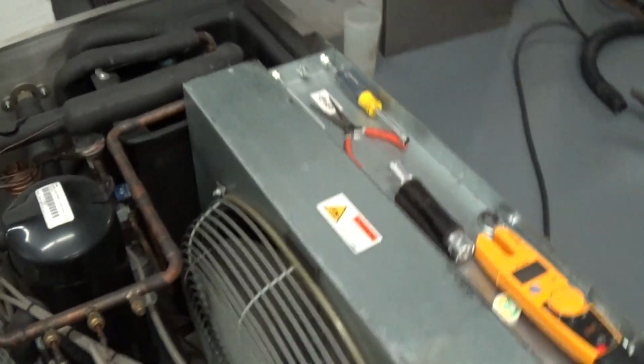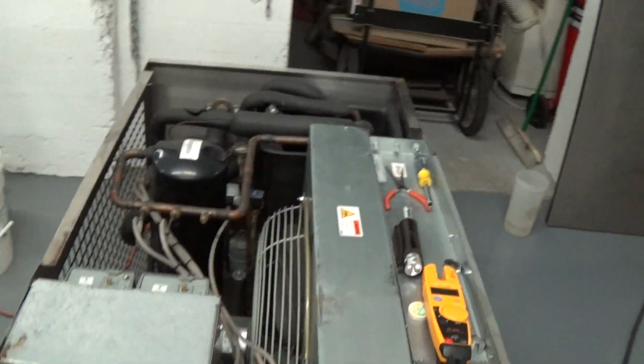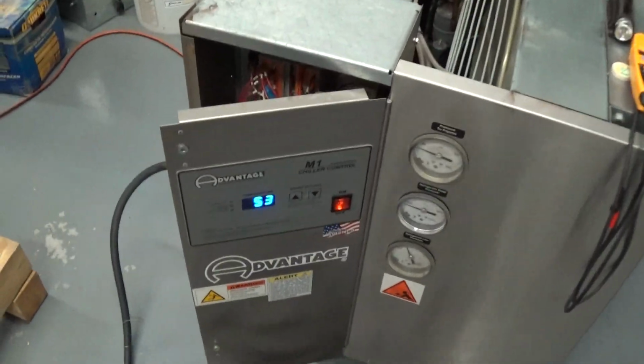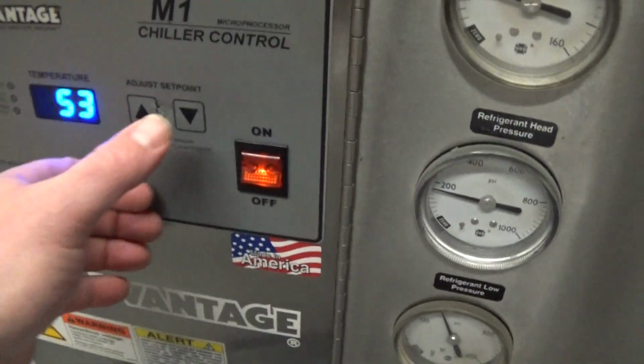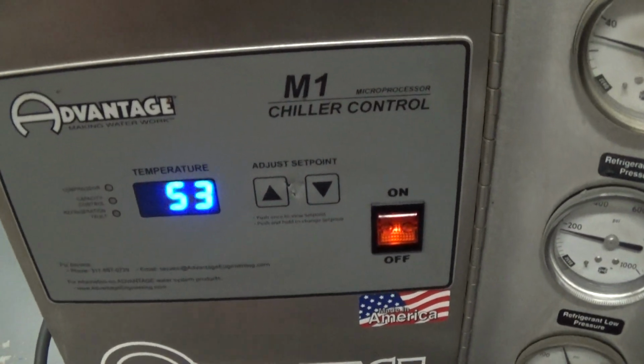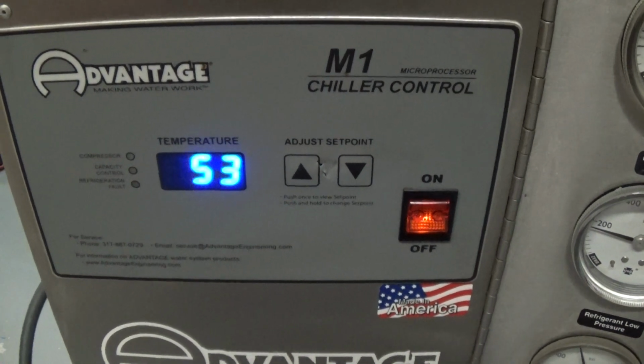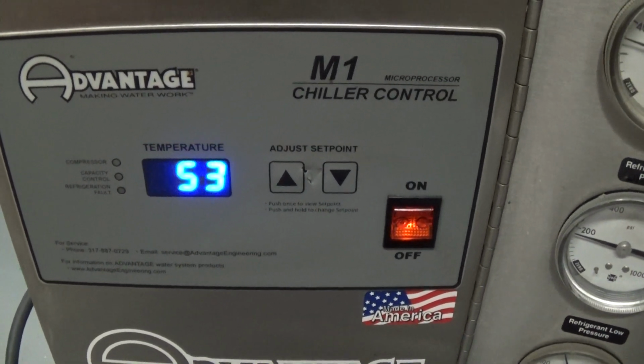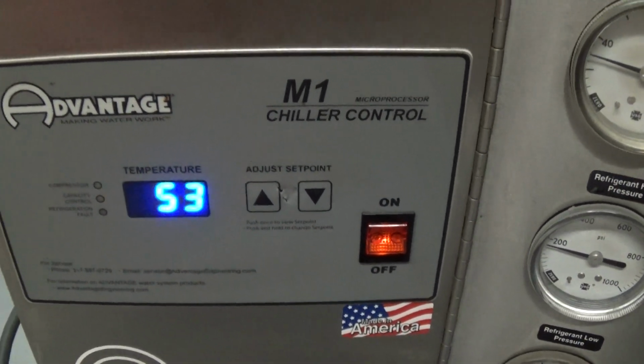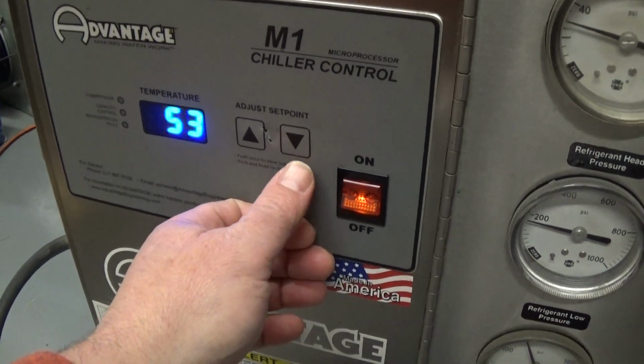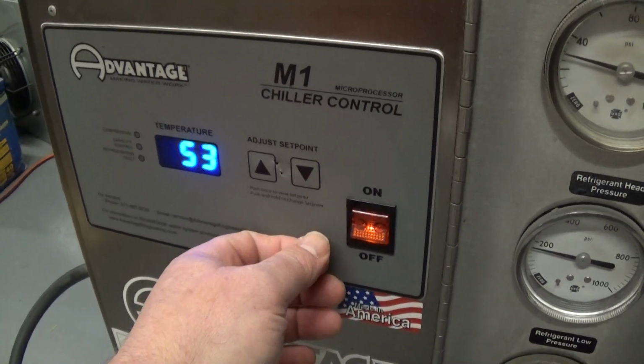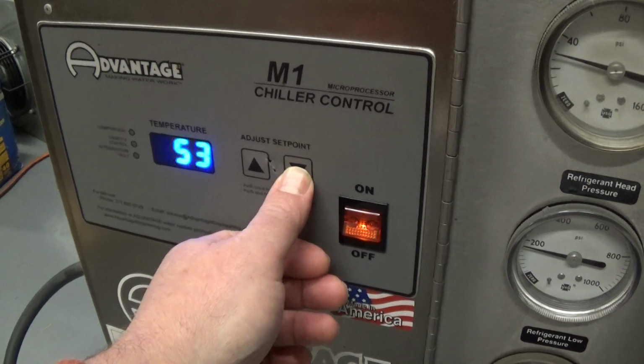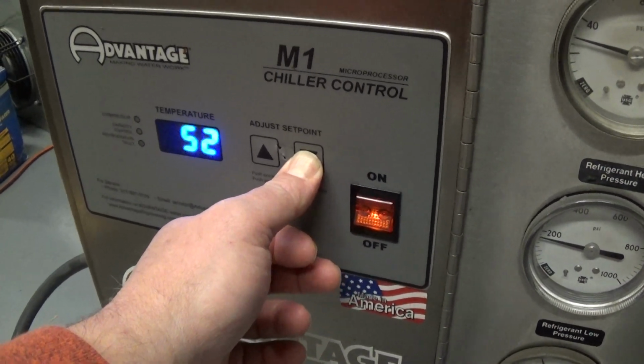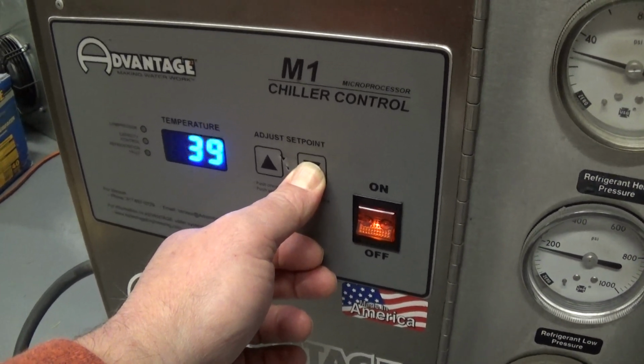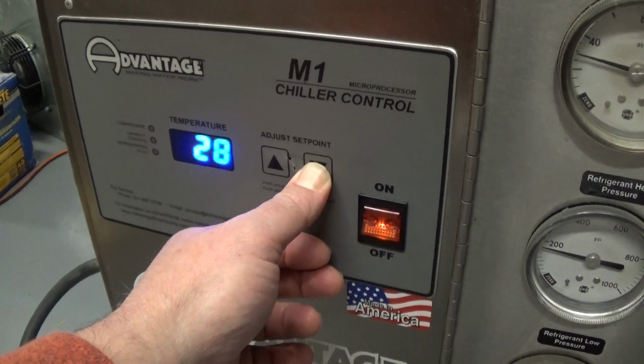Our customer needs to run this at approximately 20F. The controller itself is actually set up to go down as low as 10F. Honestly, if you want a 20F glycol temperature, I'd probably run it at 22 because there is a dead band or a differential range. But the controller is super simple. All you do is press the up and down. We'll run it down to the 20 set point.